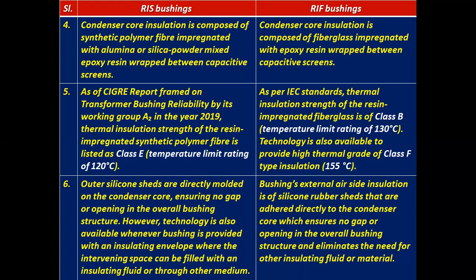Number 6, the outer silicone sheds are directly molded on the condenser core, ensuring no gap or opening in the overall bushing structure. However, technology is also available wherever the bushing is provided with an insulating envelope where the intervening space can be filled with an insulating fluid or other medium.